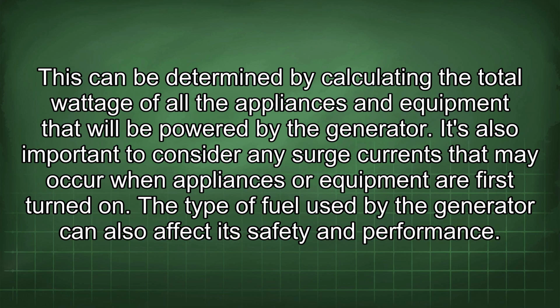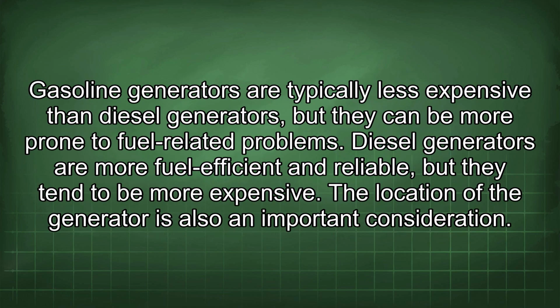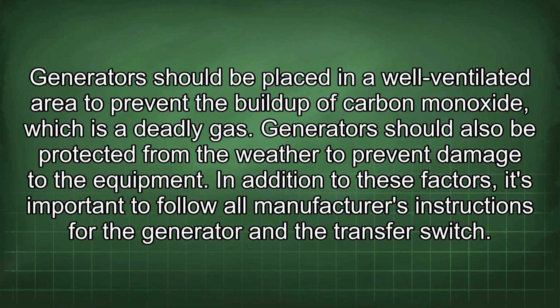on. The type of fuel used by the generator can also affect its safety and performance. Gasoline generators are typically less expensive than diesel generators, but they can be more prone to fuel-related problems. Diesel generators are more fuel efficient and reliable, but they tend to be more expensive. The location of the generator is also an important consideration. Generators should be placed in a well-ventilated area to prevent the buildup of carbon monoxide, which is a deadly gas. Generators should also be protected from the weather to prevent damage to the equipment.